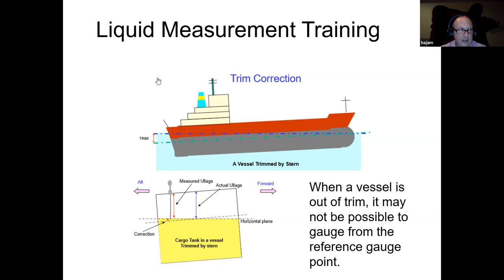It's really not recommended to try to take a tank gauge reading while the tank is active. The tank needs to be settled and calm so that it doesn't move your plumb bob around. You can actually miss the datum plate if it's moving so much. You'll think you're on the datum plate, but you're actually on the bottom of the tank, which completely throws your tank measurement off. So it's basically based on the fact that it's heavy and that it is capable of being moved around. Just because it's heavy doesn't mean it's not going to move. It should not move if the tank is stable and there's no turbulence in the tank. That's the only way I think I can answer it.